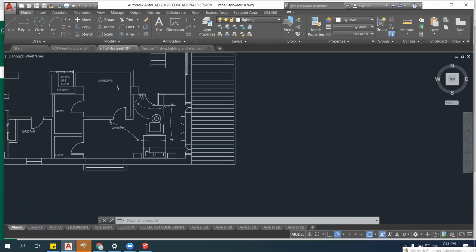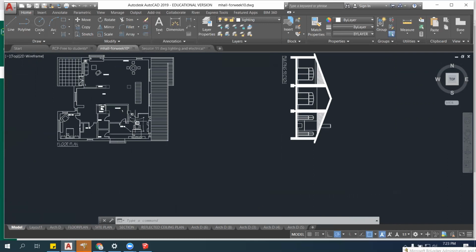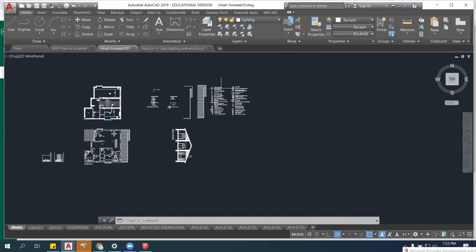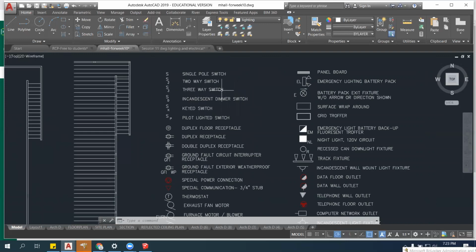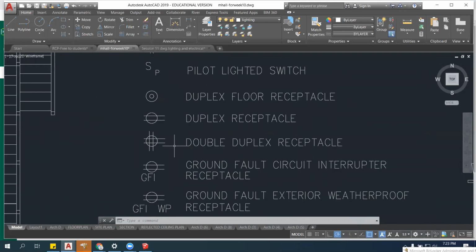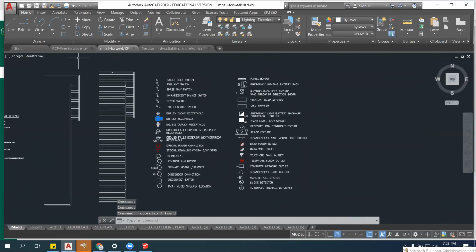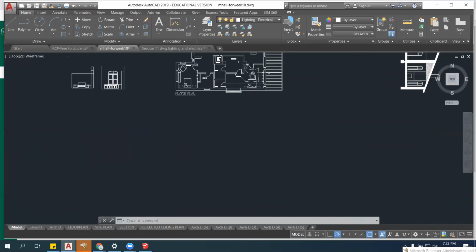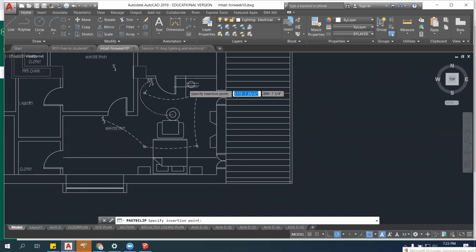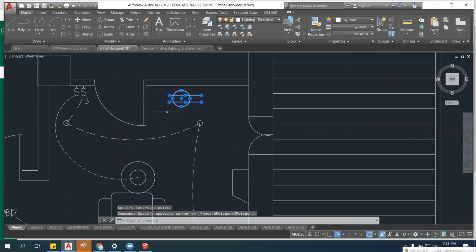All right, so every plan looks kind of beautiful like this, but there's other things happening in a room. And that is all of our plugs, right? For our iPhones and our TVs and whatever else we want. So I could have just a basic duplex receptacle that isn't ground fault because it's her bedroom, not her bathroom. I'm gonna Control C that and come back down to plan down here. A good rule of thumb for these things is every 8 feet. That's pretty standard in residential developments.